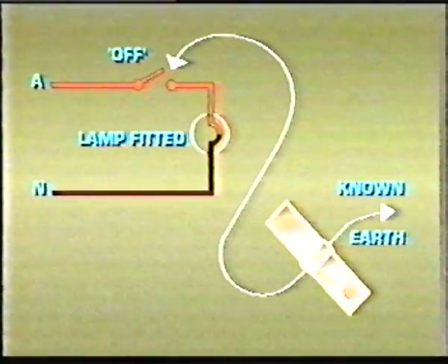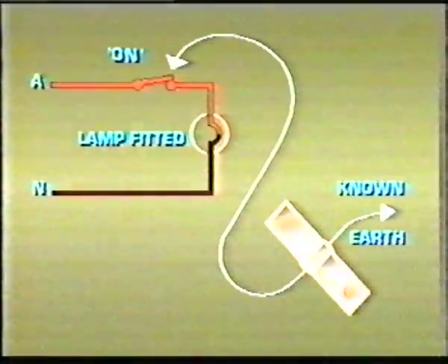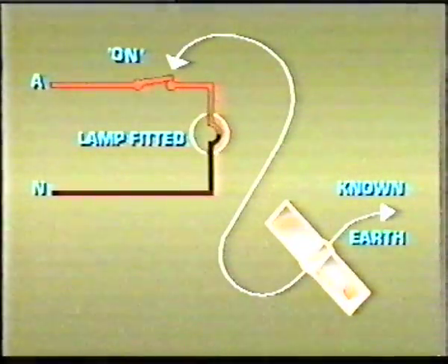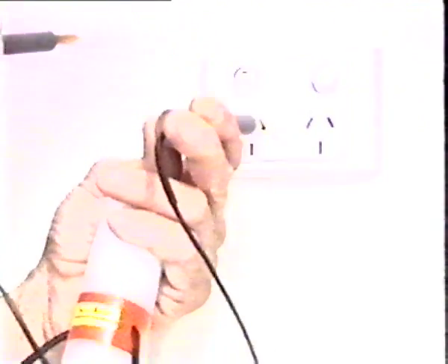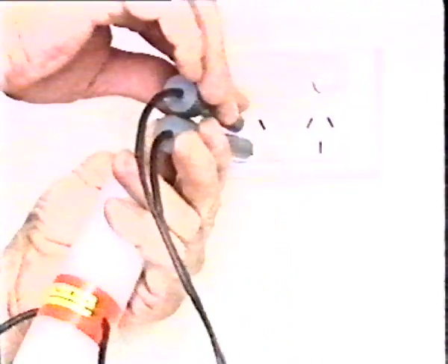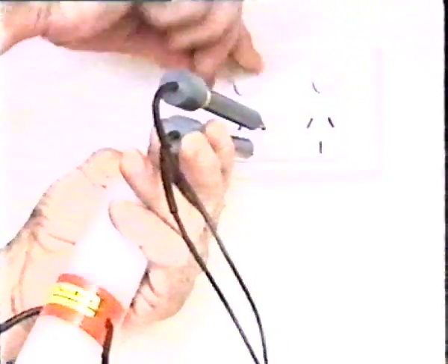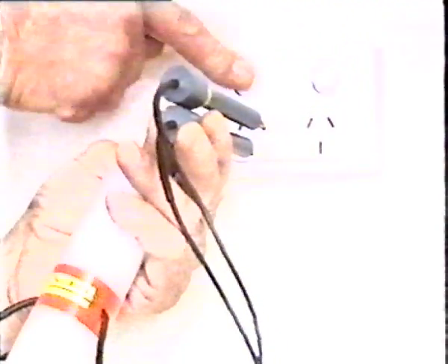To test the lamp holder or luminaire, one probe of the test lamp is connected to a known earth, and the other is connected to the load side of the control switch. The correct polarity is indicated by a normal glow of the test lamps when the switch is closed. To test a socket outlet, the test lamps are connected in turn between active and neutral, active and earth, and neutral and earth. With the switch on, and then with the switch off.